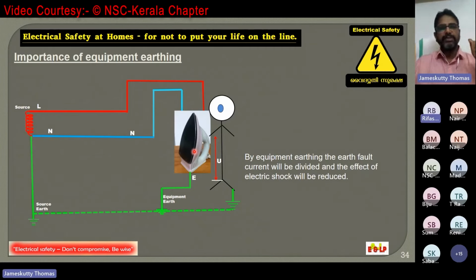Suppose we do not have such a protection device, we can still get protection up to a limit, since the earthing and human body paths are in parallel, and thus the fault current that may pass through the human body will be lesser. See here, this human body path and this earth path are in parallel, and if there is a fault current, there is a lesser chance of getting electrocuted because current is passing through this earth. So up to a limit, we will get protection. But remember, an RCCB along with earthing will always give 100% protection in such a case. I will explain the function of the RCCB in a later slide.